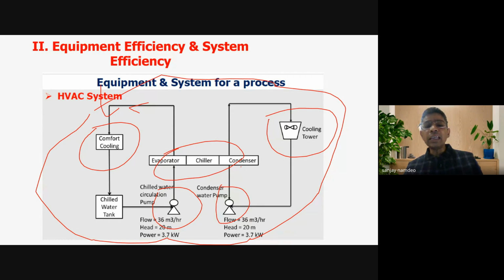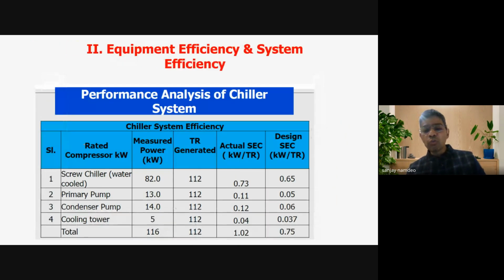So if I have to make the HVAC system efficient, my focus is not only that my chiller should be efficient. My focus should be that my entire system should be efficient. So what is the second approach? Rather than focusing on the equipment efficiency, we should focus on the system efficiency. Now, how would be the difference?